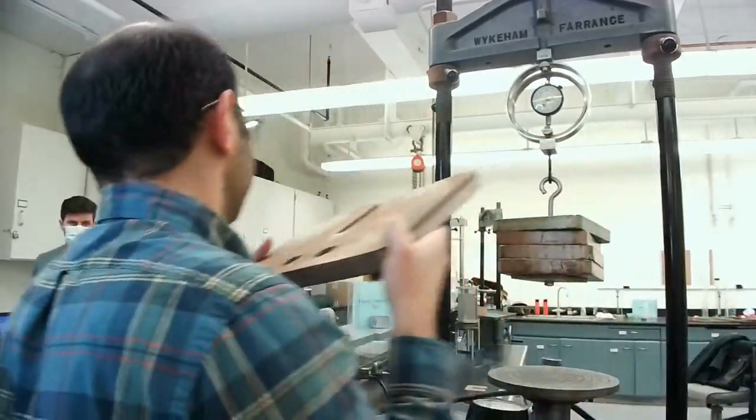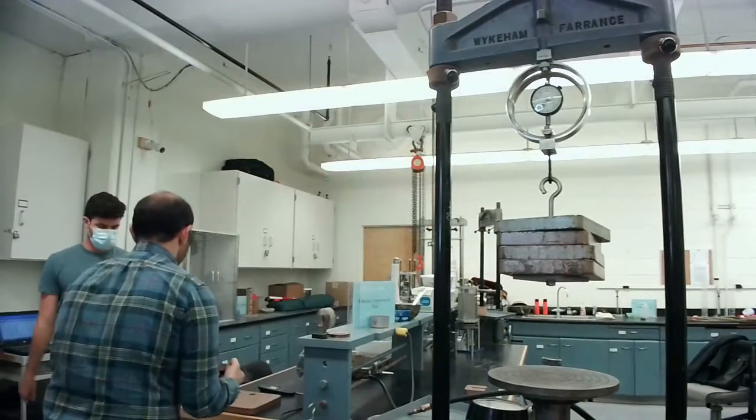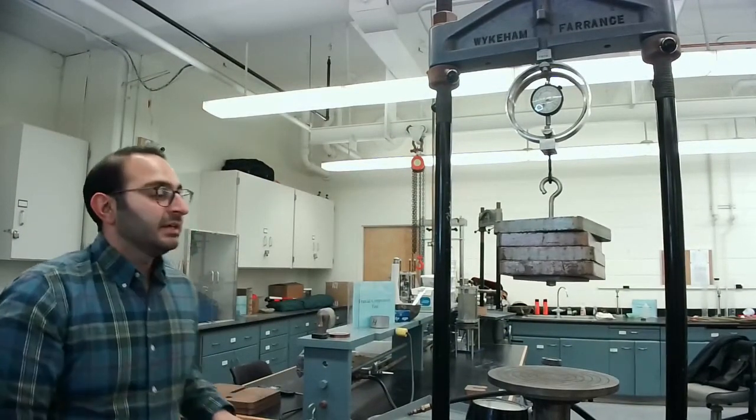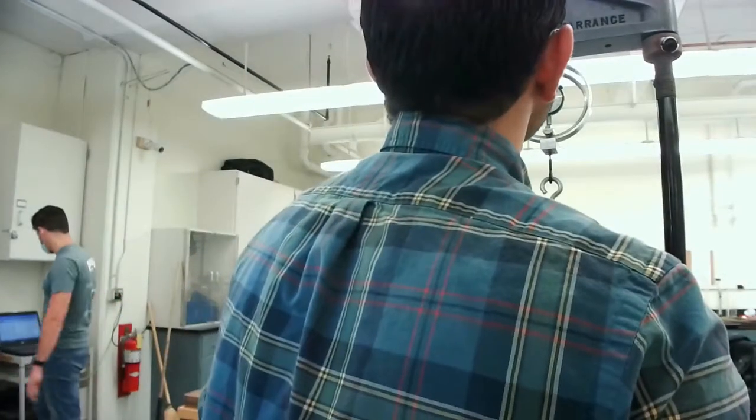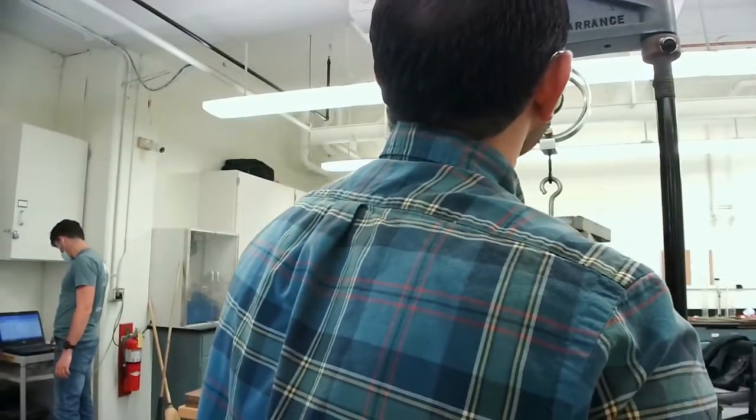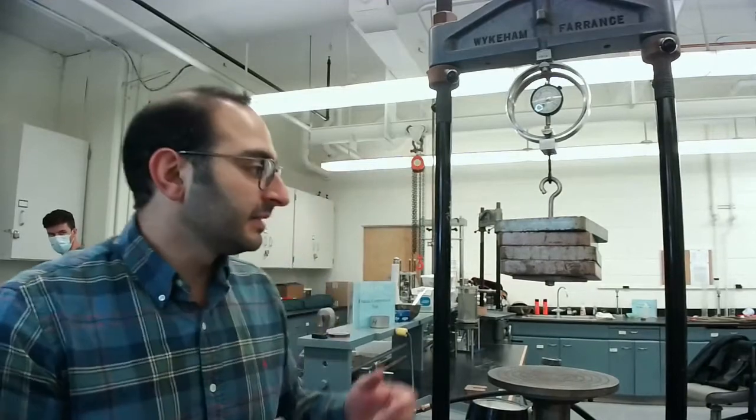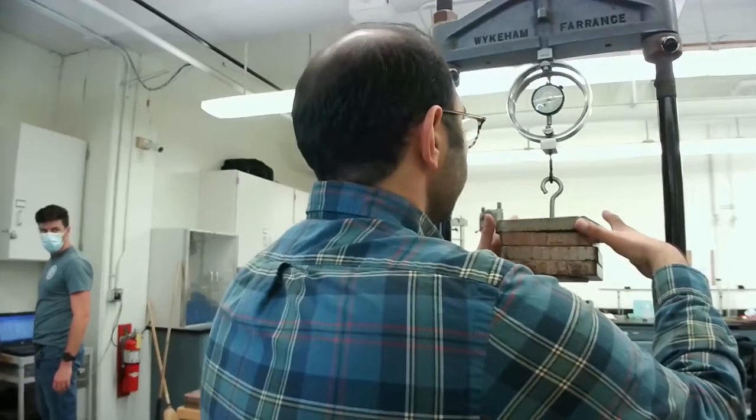I'll take this one off too, and the reading is five hundred and thirty-five. As you can see, the readings while loading and unloading are slightly different, and that's why we're doing it both ways.